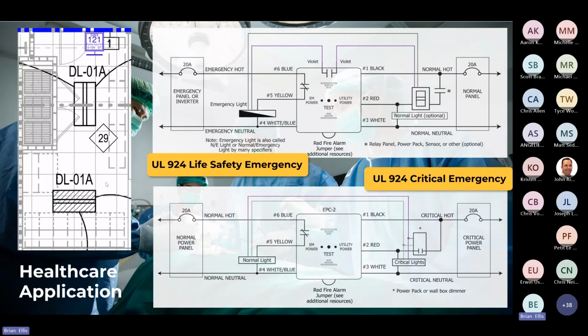Whereas with critical, we actually want the lights to work from the controls fed from critical power. So if you're ever in a circumstance where you have a lighting control device that needs to control normal and critical simultaneously, most people just provide another lighting control device, with a wall mounted aux sensor, with or without dimming, and that could be confusing for the client. So instead of doing that, you take our normal EPC, and instead of wiring it for life safety, you wire it backwards. If you look at the bottom, now instead of the normal being on the right side, we put the critical. So the critical emergency power will always be feeding the controls and feeding the critical lights. The normal will follow the critical. So we're kind of using it backwards. When you lose normal, you just lose the normal lights, but the lights will still work from your control device from critical power. So this is kind of a unique circumstance. Again, reach out to us if you want additional information on this.